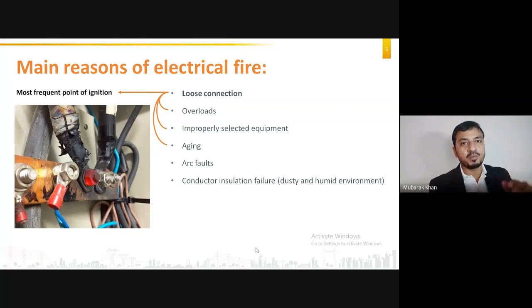They are not tightened properly, or your conductor is not of the same thickness. Like somewhere the conductor is a little bit thin, so the heating will be more at that point. If the conductor is tampered by heating or something, there will be heating at that point. Or if there is a connection and the joint is not perfect, improperly made, then there will be heating at that particular joint.